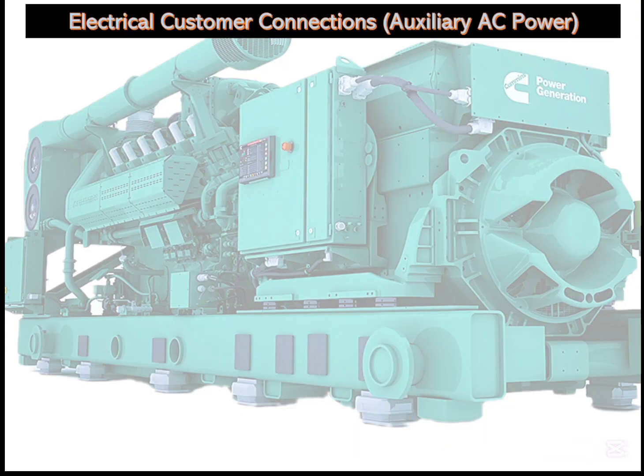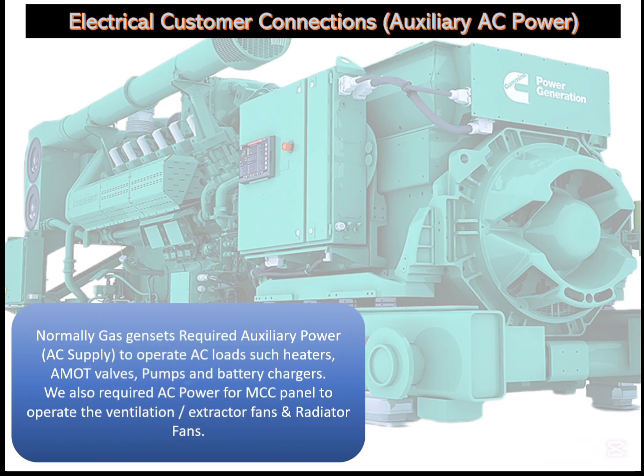Let's look at the auxiliary AC power. In gas generators, the customer is supposed to provide auxiliary power for the AC loads installed on the gensets, such as the circulation pumps. We have battery chargers. We have heating elements. Then we have motor valves and electronic thermostats. So to operate all of them, customers should supply AC power, that is 3-phase and single-phase AC power.